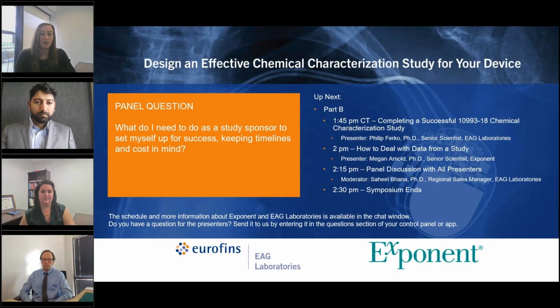You may need to then run a simulated use leachables test or a targeted test for specific chemicals, and then you don't have time to successfully do that. So I always encourage, if you have 3 months left until your submission deadline, do not start your chemical characterization test then. You should start it 6 months earlier, if possible. So that's my advice for success: giving the experts, the chemists and the toxicologists, the proper time.